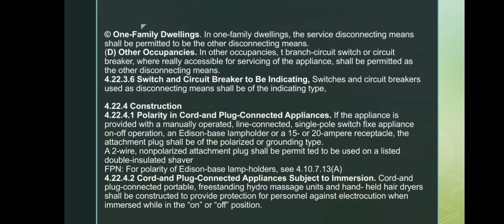For cord and plug connected appliances with a single pole on-off switch, an Edison base lamp holder or a 15 or 20-ampere receptacle, the attachment plug must be polarized or grounding type. A non-polarized two-wire plug is only allowed for a listed double insulated shaver. Portable hydromassage units and handheld hair dryers must be built so that they protect people from electric shock even if the appliance is accidentally immersed in water, whether it is turned on or off.